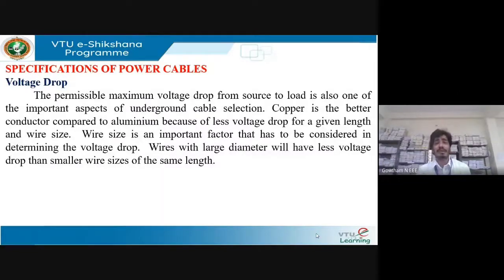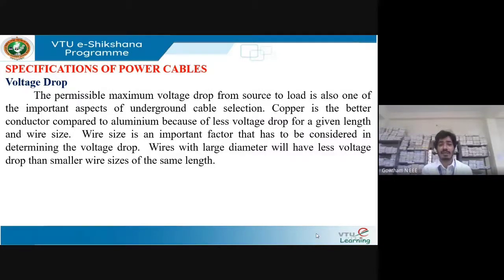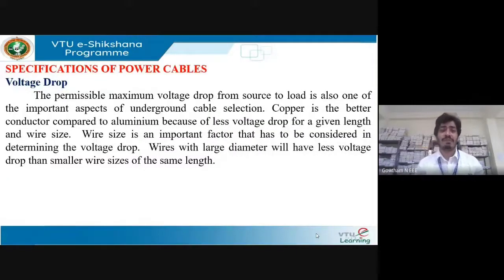The permissible maximum voltage drop from source to load is also important in selecting a UG cable. Copper is a better conductor than aluminum because it has less voltage drop for a given length and wire size. Wires with larger diameter have less voltage drop than smaller wire sizes of the same length.